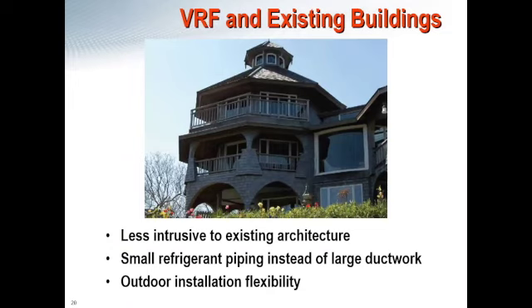I've actually worked on a lot of residential projects where the customer may not want to see the outdoor unit, and we are able to hide it all the way behind a barn or a garage somewhere on the property, dig the refrigerant line underground, run it a significant distance into the house, and have no operational issues. So really, the flexibility of the VRF installation is one thing that I want to really stress to you guys. It's a main advantage over a lot of typical HVAC technologies.